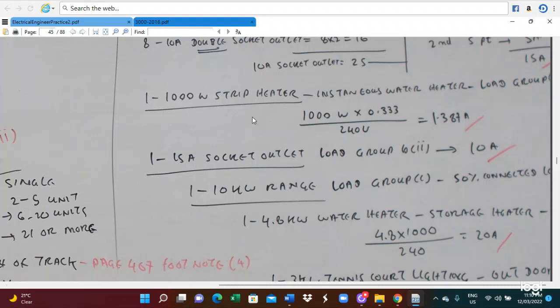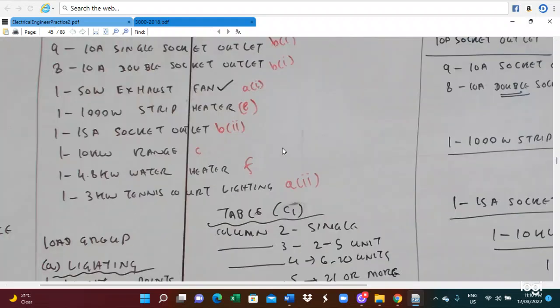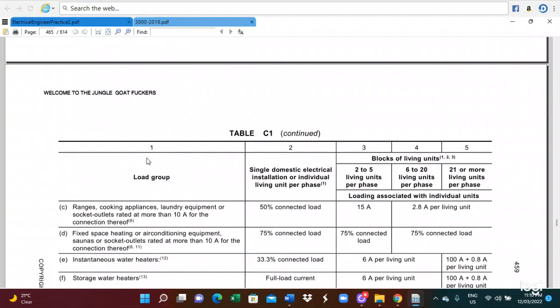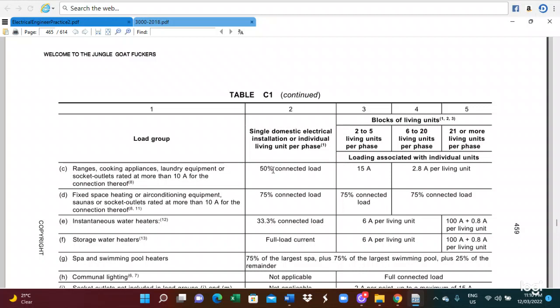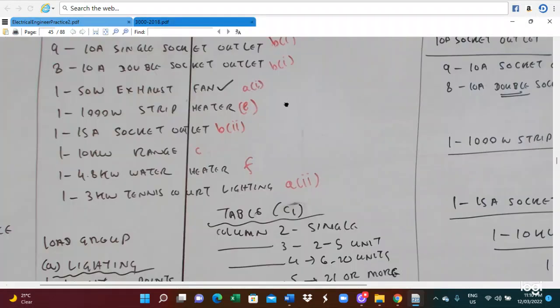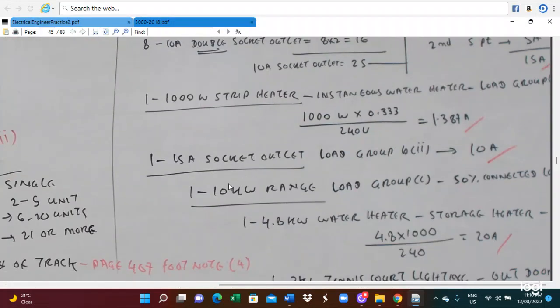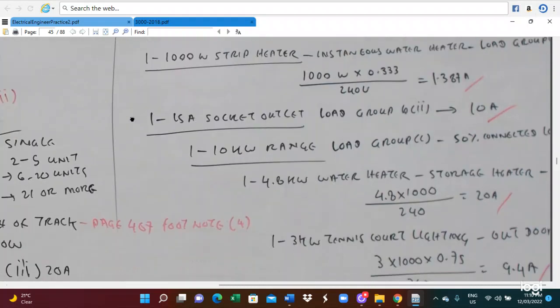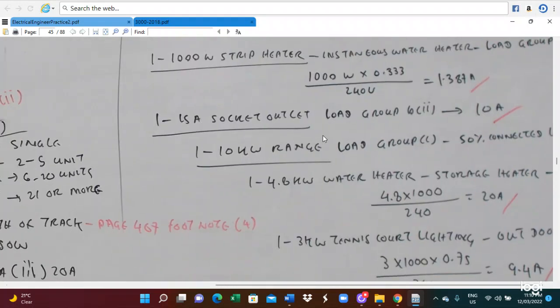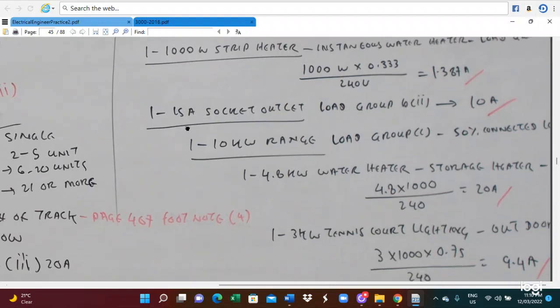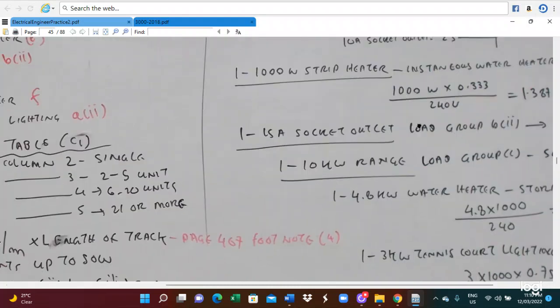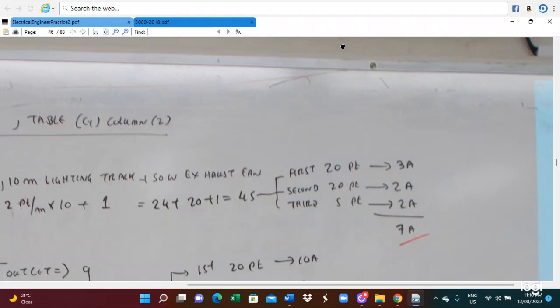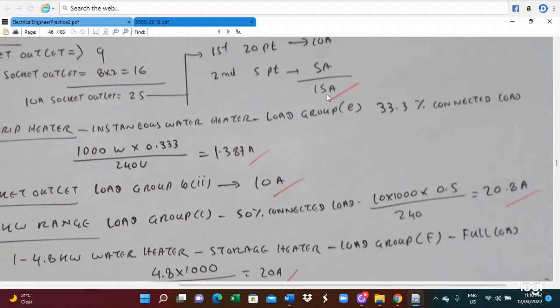Another thing is the 10 kilowatt electric range. The 10 kilowatt electric range is load group C. So for the electric range we have to take the 50% of the connected load. So 50% of the connected load here we calculated. 50% of connected load for the 10 kilowatt range, so we multiply by 50%. So 10 multiplied by 10 power 3, multiplied by 0.5 and divided by 240 for the current. This is the way we calculate the electric range current. So the electric range current is 20.8 ampere.